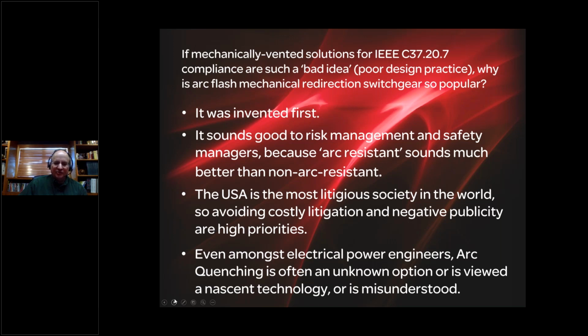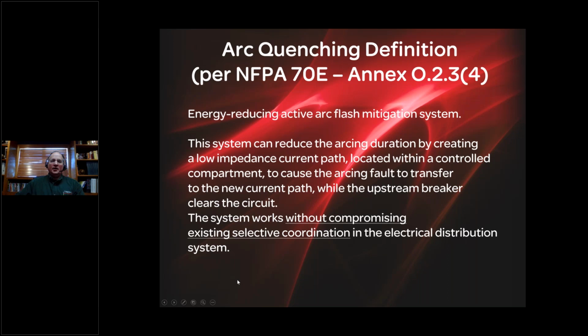And even amongst electrical power system engineers, I believe arc quenching is still often an unknown option. Even though arc quenching is defined in NFPA 70E and Annex O, and it's approved by the National Electric Code in NEC 240.87, it's still often not well known, or it's viewed as new technology, or it's just misunderstood. The definition of arc quenching out of NFPA 70E is a system that reduces the arcing duration by creating a low impedance current path within a controlled compartment that causes the arcing fault to transfer to a new current path. And this always works without compromising the existing electrical coordination, the selective coordination of the overcurrent protection devices.